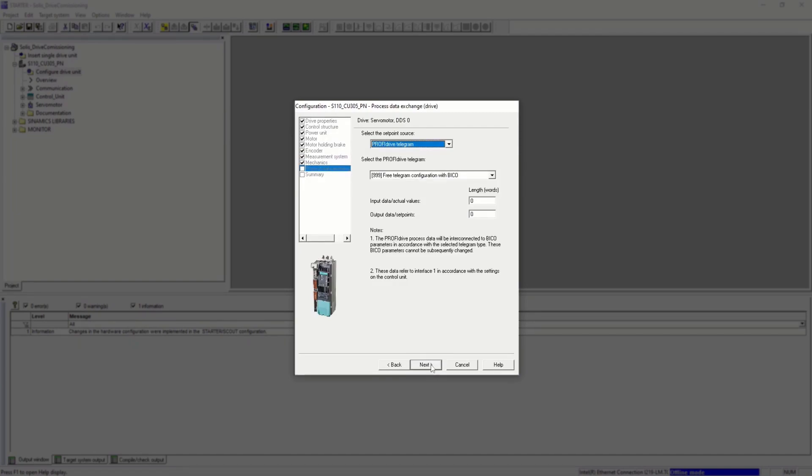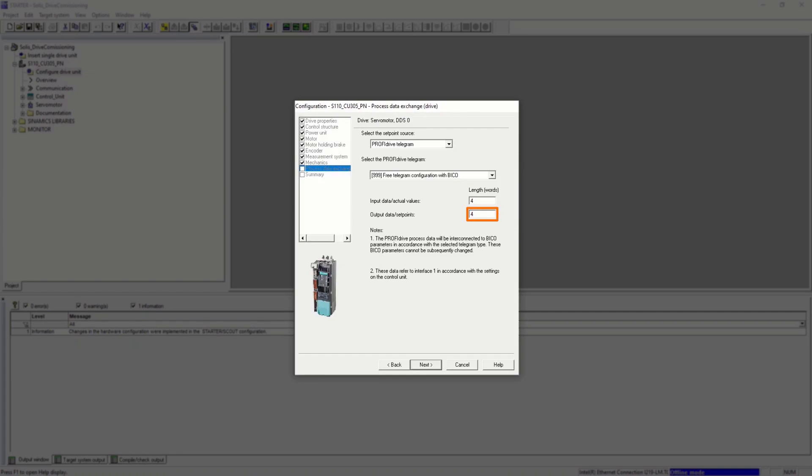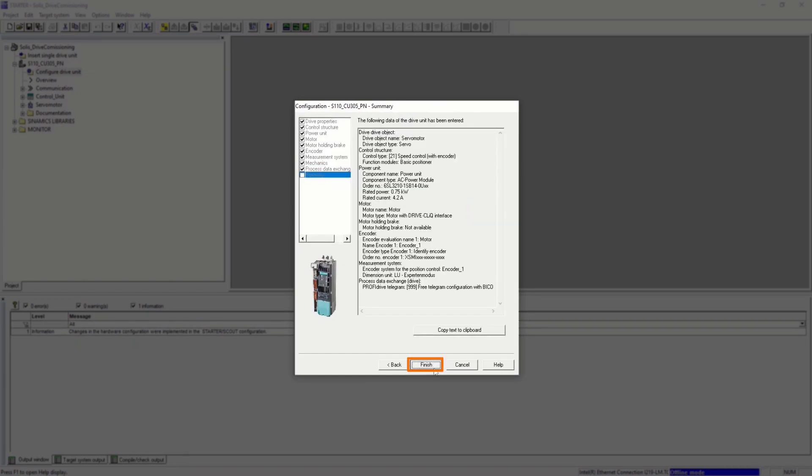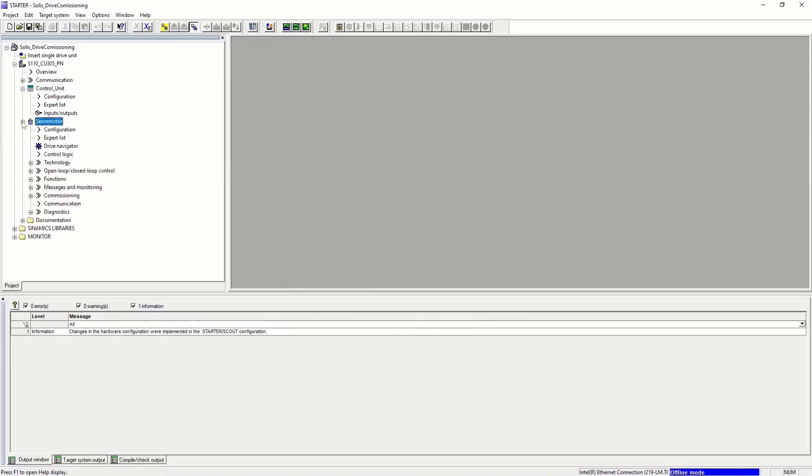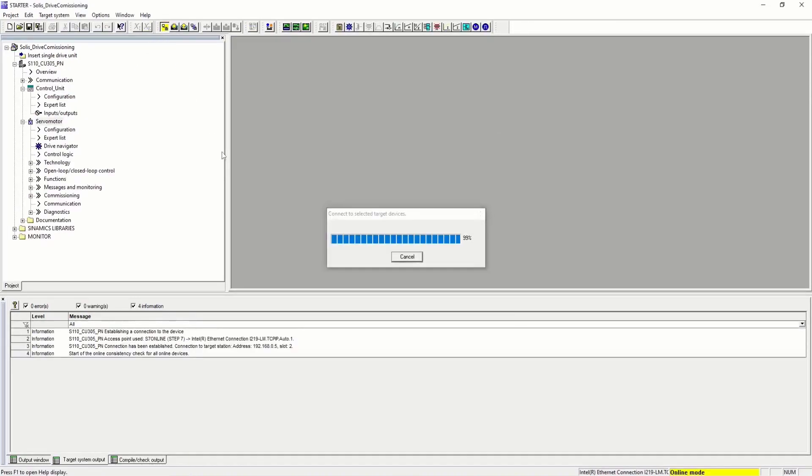For the communication interface with the PLC, we need to set a ProfiDrive telegram. A free telegram means we can use any number of words for input and output data. A 4-to-4 telegram can afford a basic position application. Now that the servo motor is created, let's go online with the device.